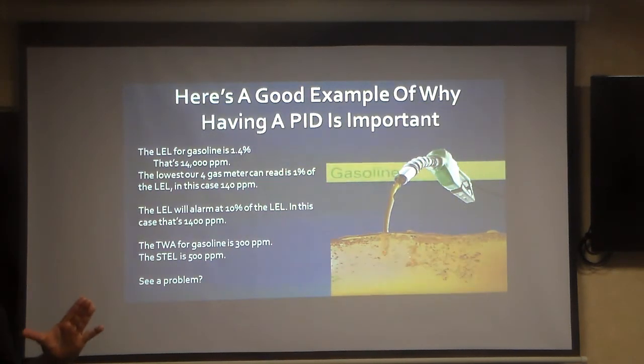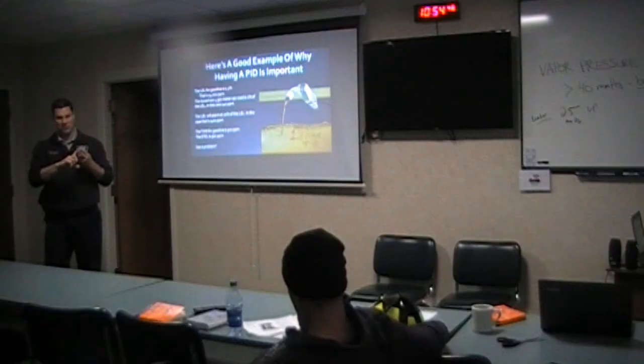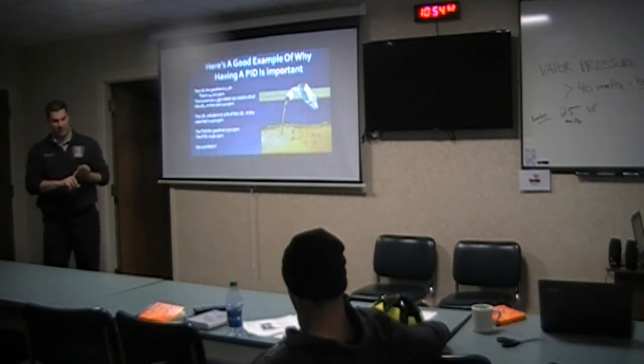Remember, the 4-gas meter has limitations. It can only tell you what it's designed to tell you. It can tell you what the oxygen concentration is. It can tell you whether or not there's an explosive atmosphere. It can tell you how much carbon monoxide we have, and it can also tell you how much hydrogen sulfide we have. But it can't tell you anything else. That's why the PID is helpful.